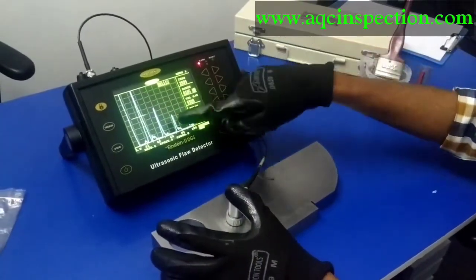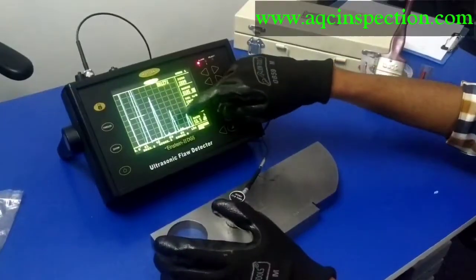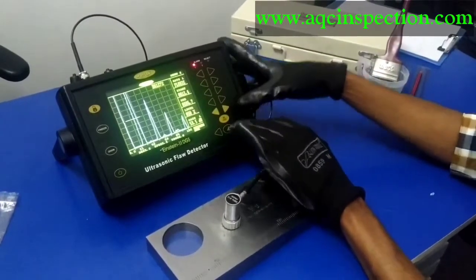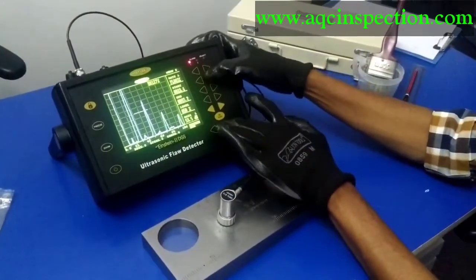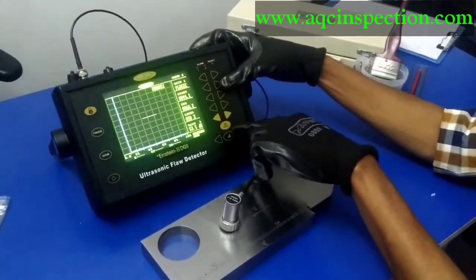Since we know the thickness of the V1 block as 25, I am going to set this as 25 mm. I am getting 24.3. So I will adjust a little bit more. 24.6, 25, 25.2. There will be a deviation which is mentioned as a tolerance in the standards. I am getting other three backwalls which is at 50 mm, 75 mm and 100 mm. You can check this using the gate, moving the gate to the second backwall. See the value is right here 50.